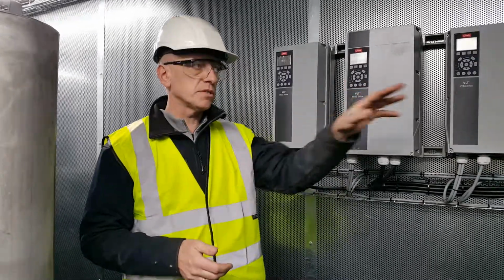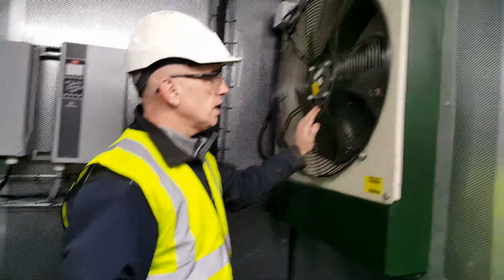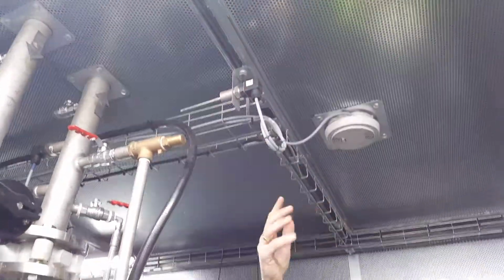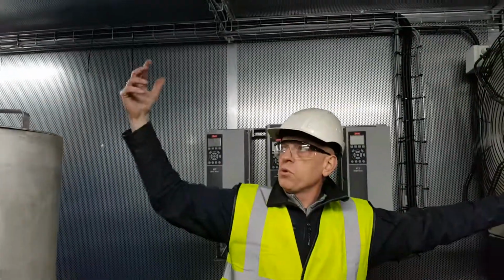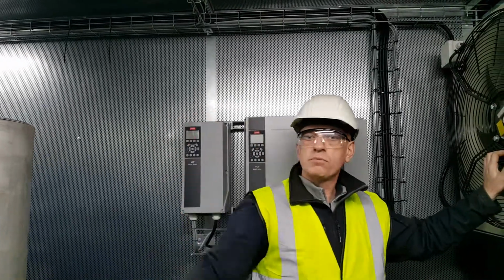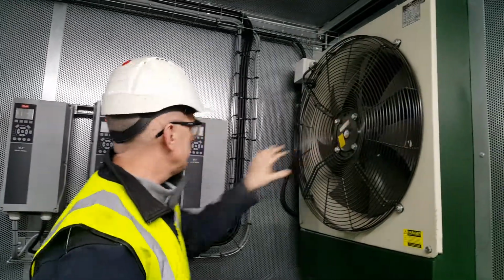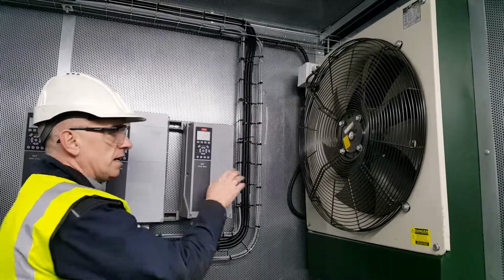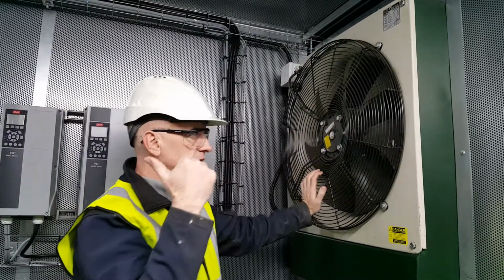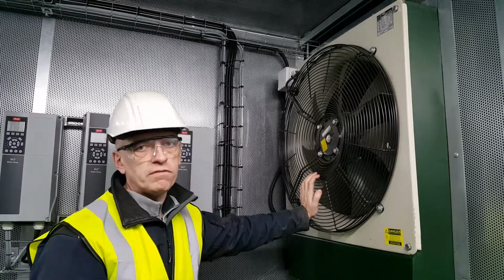We'll show you what we do to the engine to make it very user-friendly from both a maintenance and commissioning point of view. We're going to start here on the air out. We have an air temperature sensor, a PT100, which gives a reading both remotely and locally as to the room temperature inside the engine. We have a Raptor fan here fed by a VSD. The air out and air in are both silenced, so the engine runs very smoothly.